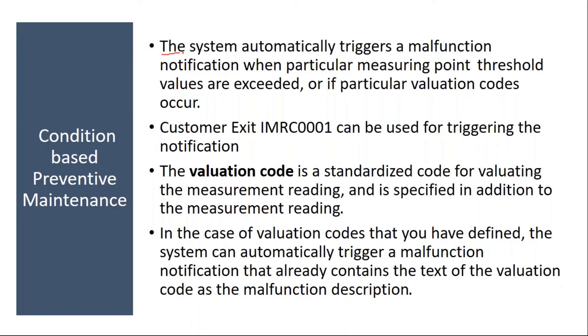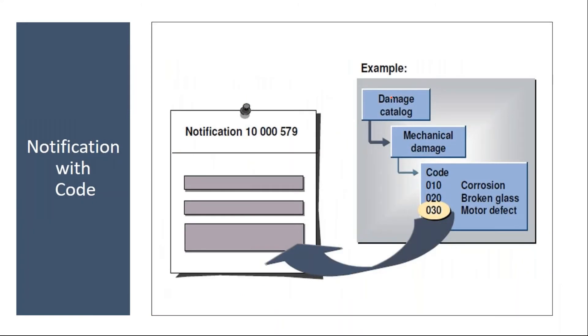The system automatically triggers a malfunction notification when a particular measuring point's threshold values are exceeded, or if a particular valuation code occurs. When they assign a valuation code in the measurement document, the system automatically triggers a notification for the preventive maintenance activity. From this notification, they will convert it to an order and then perform the preventive maintenance. I will show you this in the system.